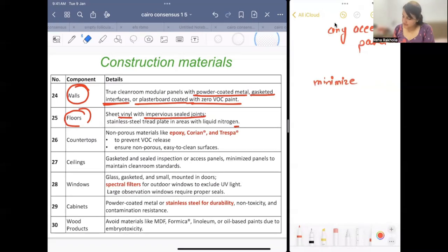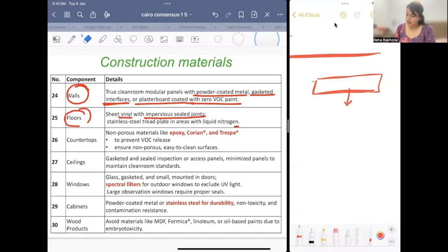Point 26 is countertops: flat surfaces like in kitchen or laboratory where we work, made of epoxy, Corian, to prevent VOC release and ensure non-porous, easy to clean surfaces. Ceiling should have minimum access panels, used for maintenance or changing filtration, and these should be gasketed and sealed.